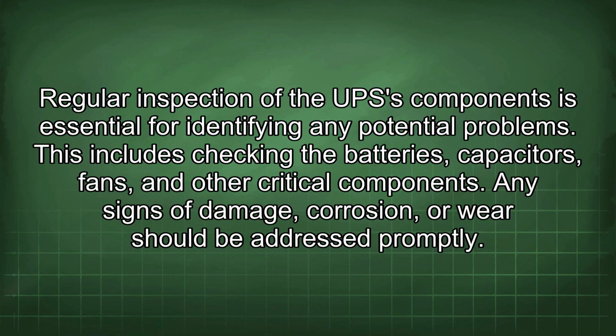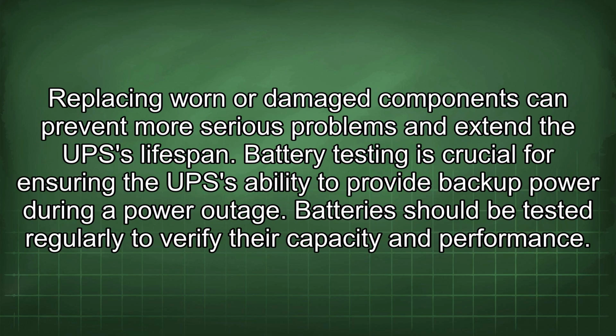Regular inspection of the UPS components is essential for identifying any potential problems. This includes checking the batteries, capacitors, fans, and other critical components. Any signs of damage, corrosion, or wear should be addressed promptly. Replacing worn or damaged components can prevent more serious problems and extend the UPS lifespan.